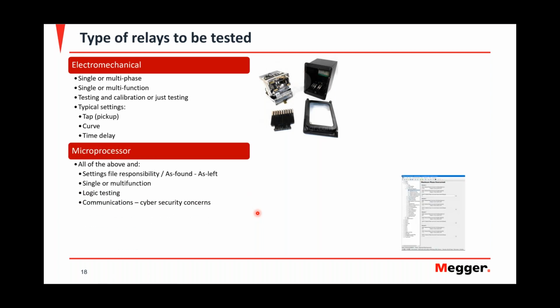On microprocessor relays, you're still concerned with all the things above, but there's also the settings file responsibility. You get the call, "Hey, I got to test the relay." Hey, who's responsible for the settings file? Is our firm responsible for the settings file, or do I get it when I'm on site? Can I have it before that? Am I testing the as found and the as left settings? What exactly is my responsibility when it comes to microprocessor relays?